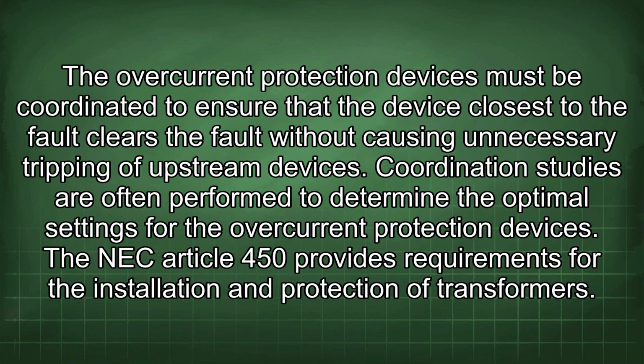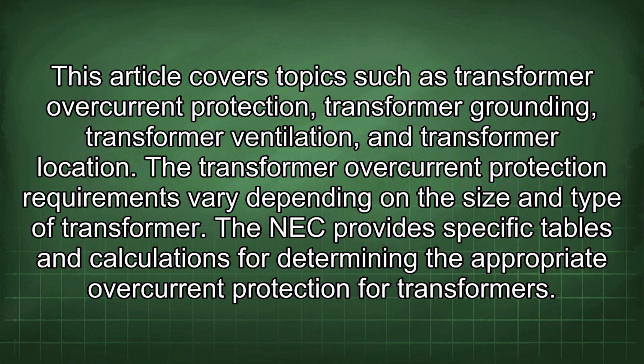The overcurrent protection devices must be coordinated to ensure that the device closest to the fault clears the fault without causing unnecessary tripping of upstream devices. Coordination studies are often performed to determine the optimal settings for the overcurrent protection devices. The NEC Article 450 provides requirements for the installation and protection of transformers. This article covers topics such as transformer overcurrent protection, transformer grounding, transformer ventilation, and transformer location.